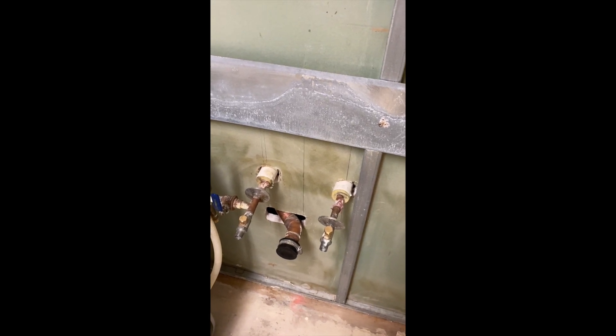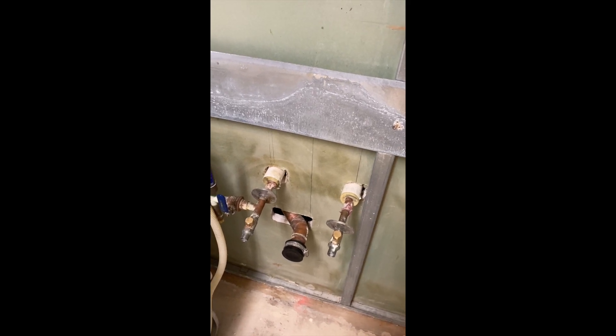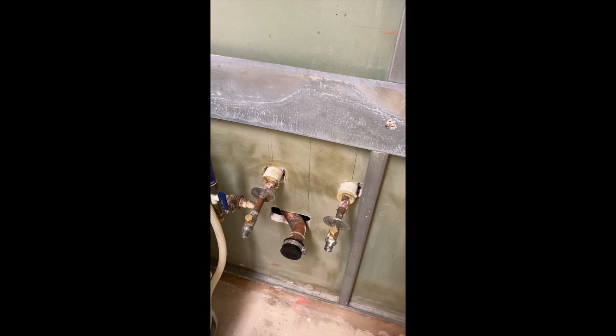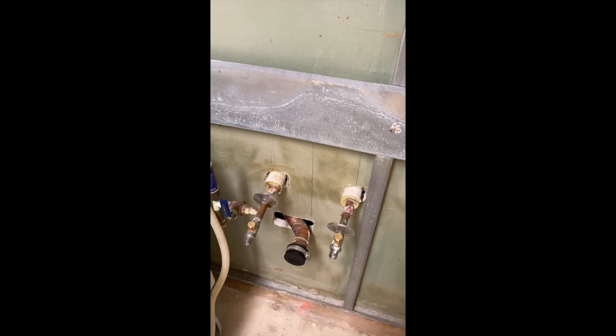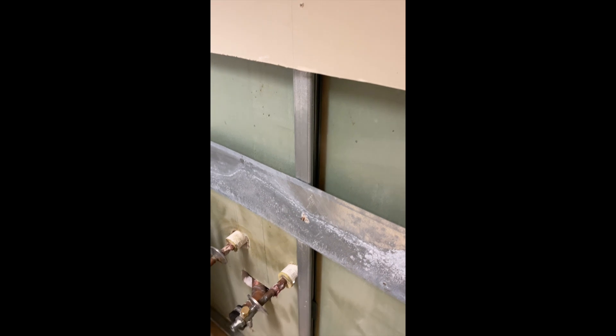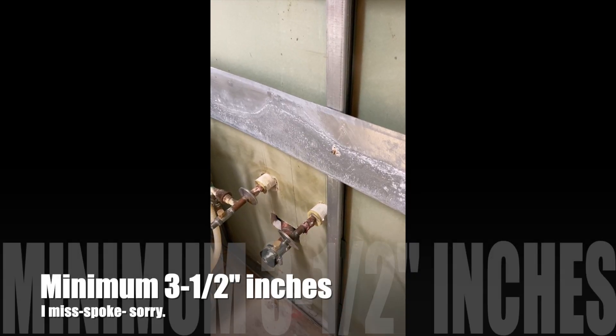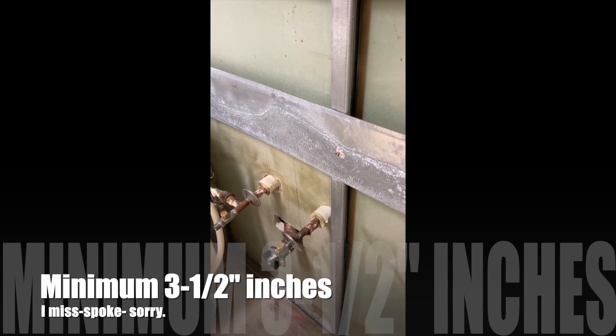So if you're working on a project and you have shaft walls with penetrations through those shaft walls, please make sure that you are checking the fire stop at the shaft liner side, and that you have a fire stop detail that allows for the use of a narrow framing member. A lot of fire stop details say they're applicable for a wall that has a minimum two-and-a-half-inch framing member. This clearly is not three and a half inches.